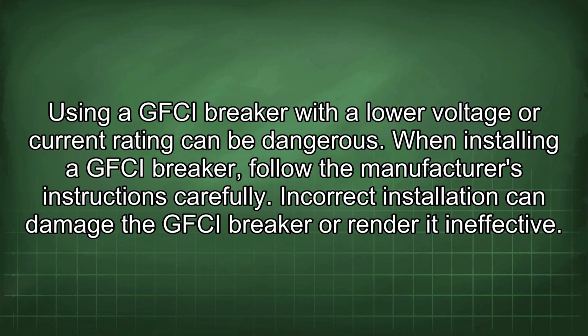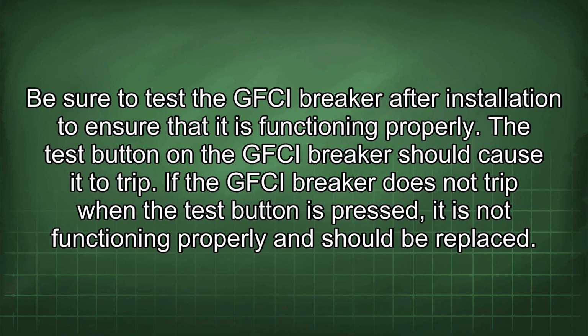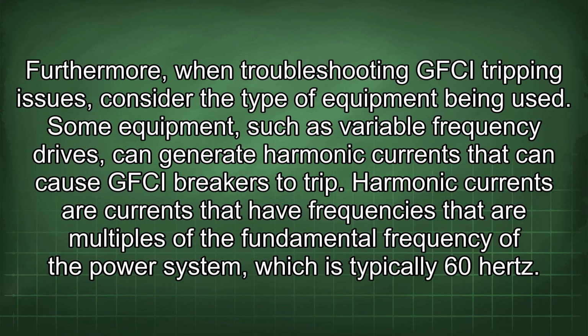When installing a GFCI breaker, follow the manufacturer's instructions carefully. Incorrect installation can damage the GFCI breaker or render it ineffective. Be sure to test the GFCI breaker after installation to ensure that it is functioning properly. The test button on the GFCI breaker should cause it to trip. If the GFCI breaker does not trip when the test button is pressed, it is not functioning properly and should be replaced. Furthermore, when troubleshooting GFCI tripping issues, consider the type of equipment being used.